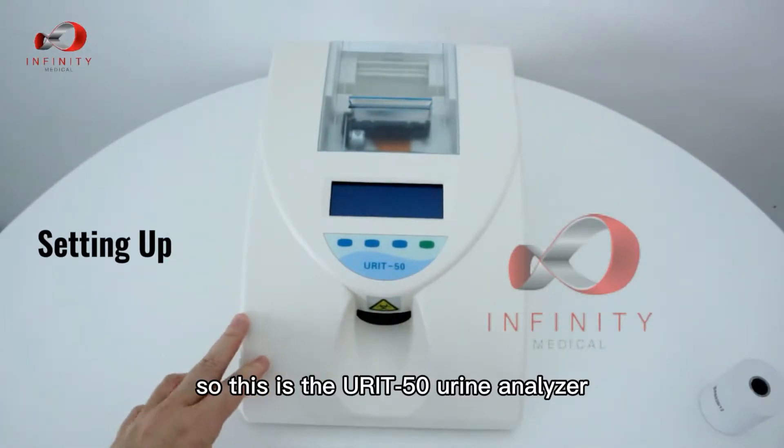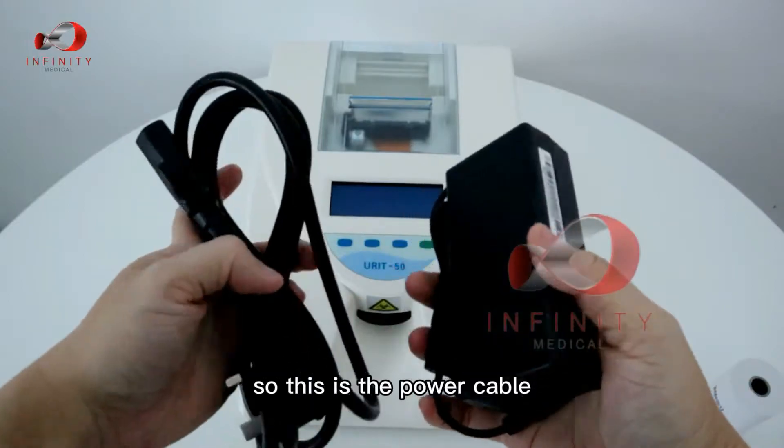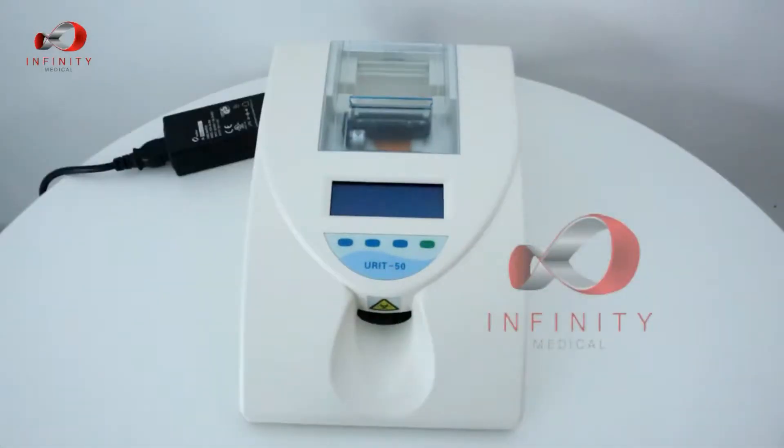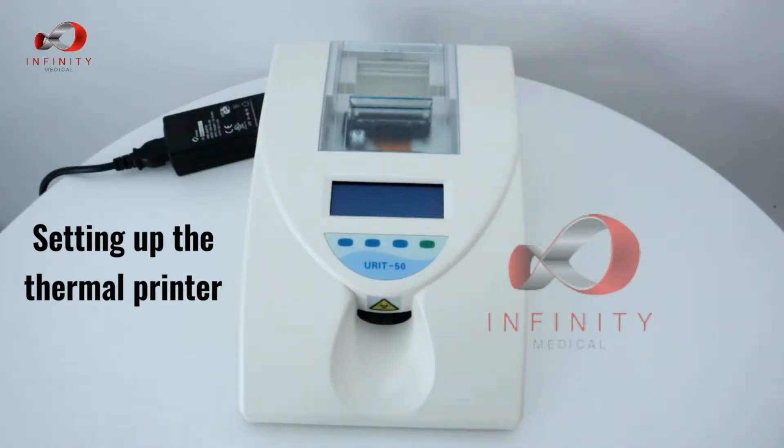This is the URIT-50 urine analyzer. To set up, first connect it to the power adapter — this is the power cable. Before turning on the device, ensure that there is thermal paper loaded for the thermal printer.